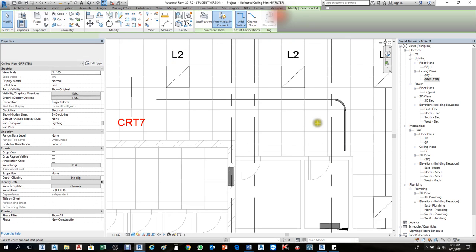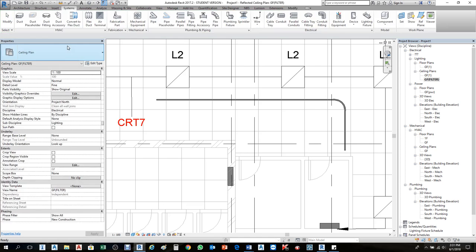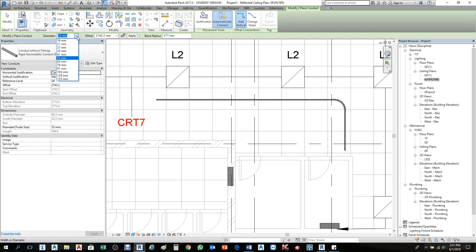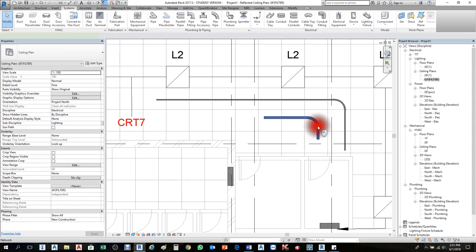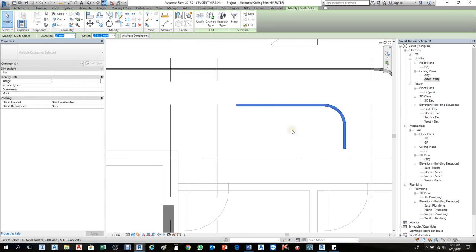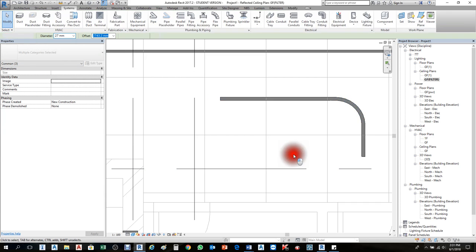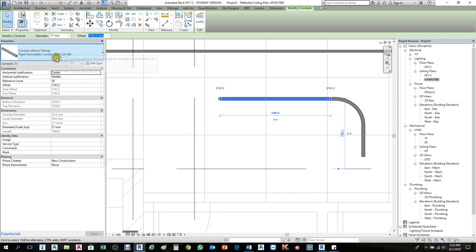When drawing conduit again, I need 25mm. If I change to another type — for instance RNC 40 — and try to select 25mm, it's not available, only 27mm. When I try to change the size to 25mm it won't change, because by default it comes as 27mm. To fix this, select the conduit, find its family name — this one is RNC 40 — then go to the Electrical settings.